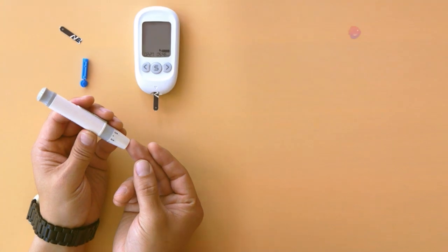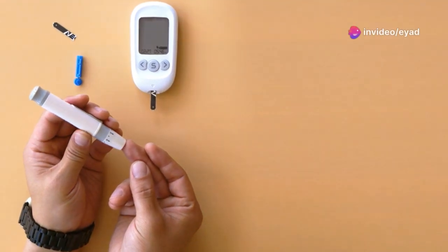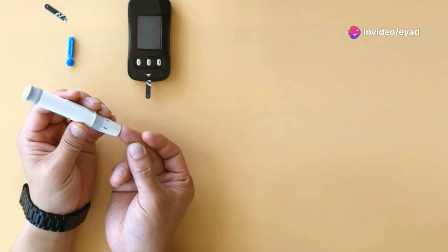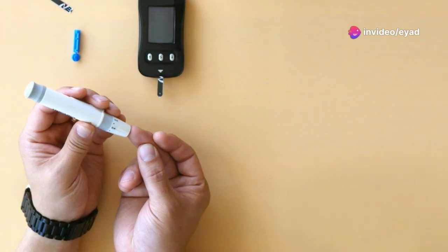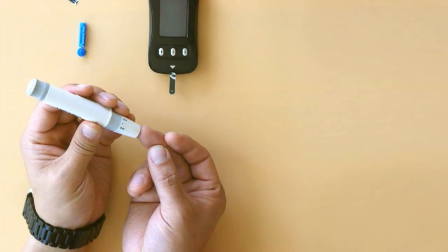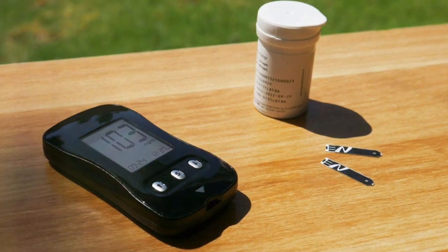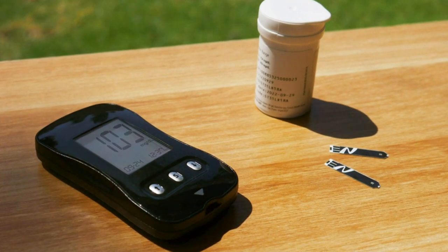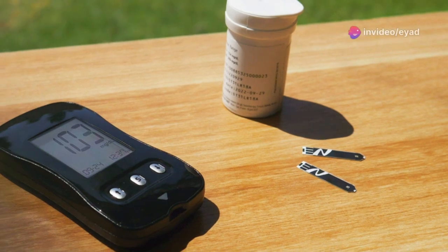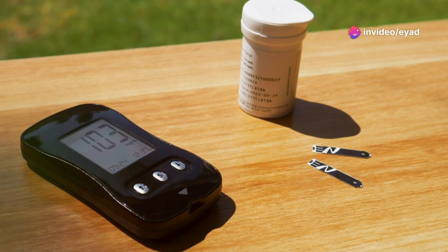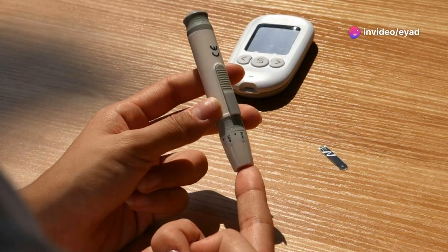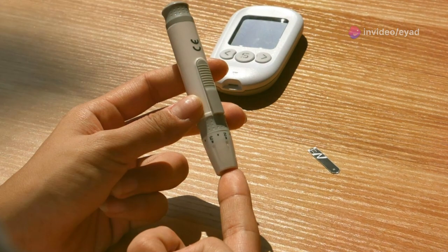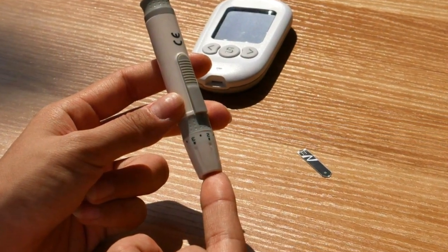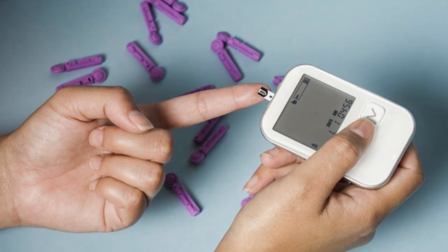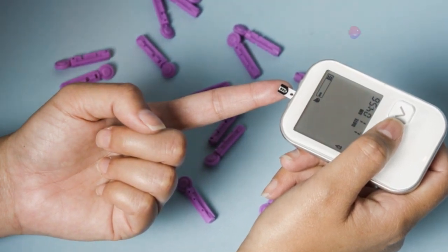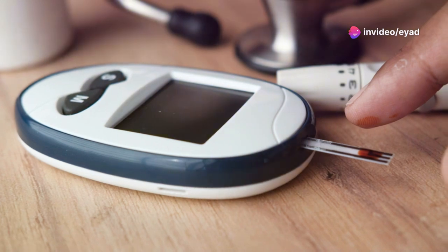Glucose meters rely on calibration curves to convert the electrical signals from test strips into blood glucose readings. These curves ensure that the readings are accurate and reliable, providing users with the confidence they need to manage their health. These meters are typically calibrated at the factory using standard glucose solutions, and users may need to recalibrate them periodically using test strips provided by the manufacturer. This periodic recalibration is essential to maintain the accuracy of the device over time.